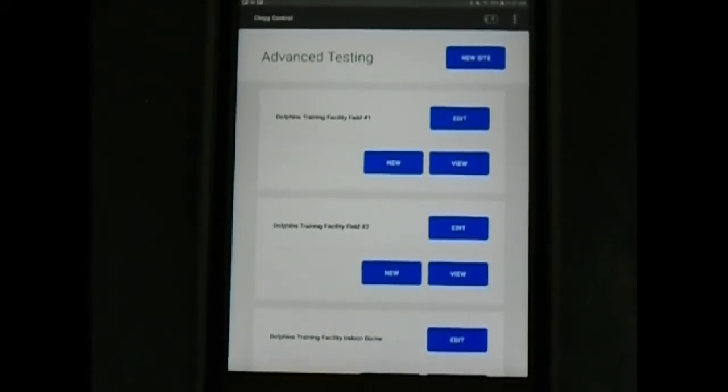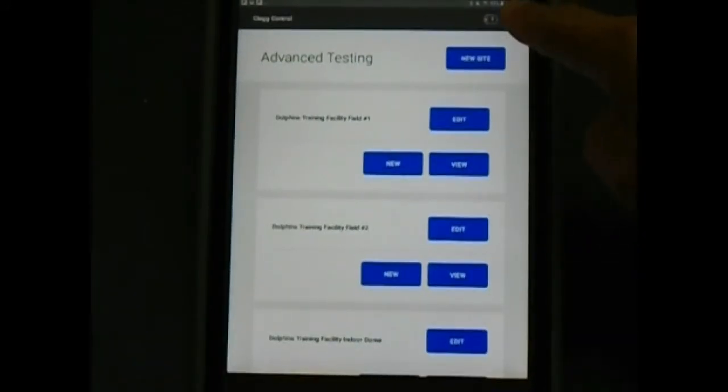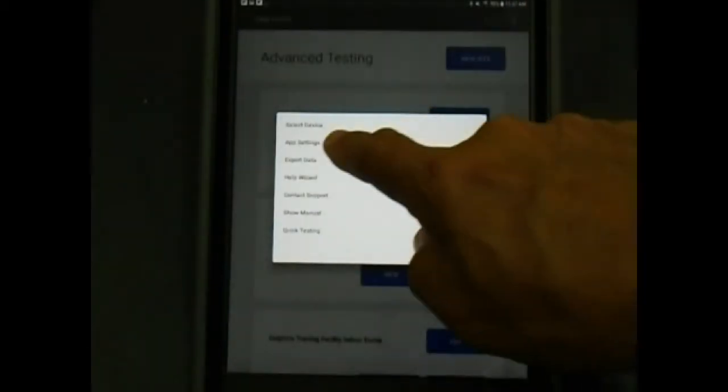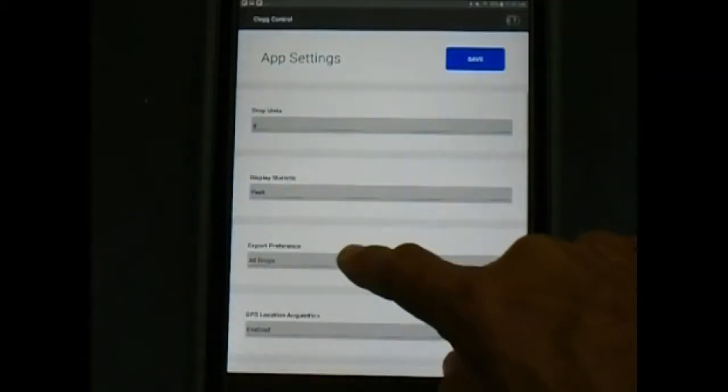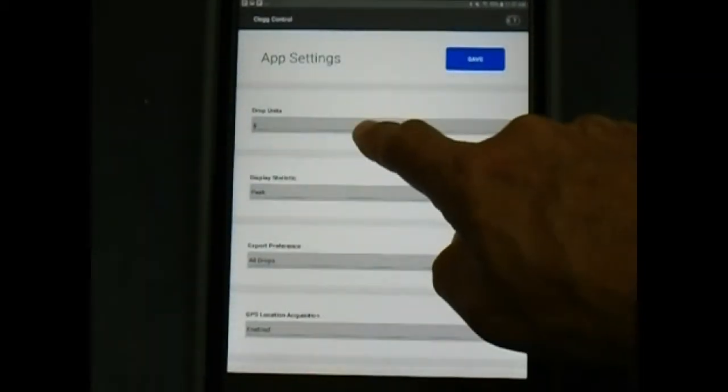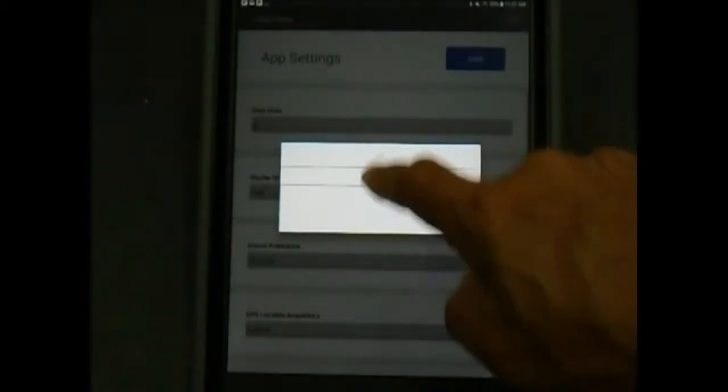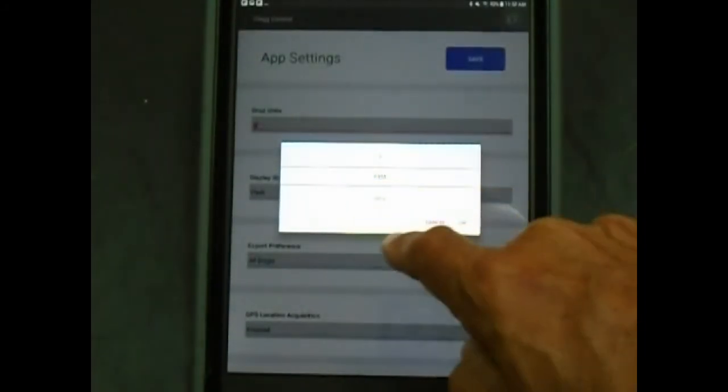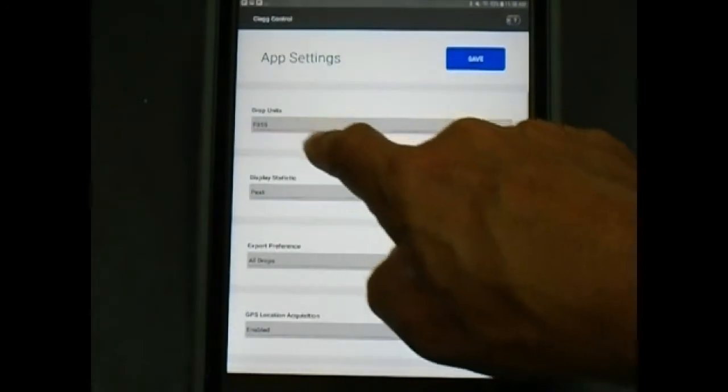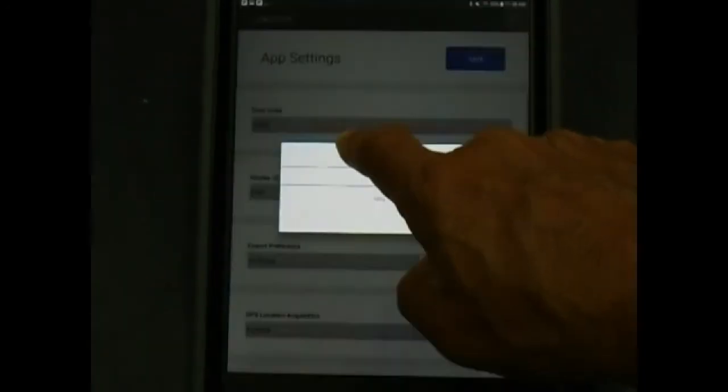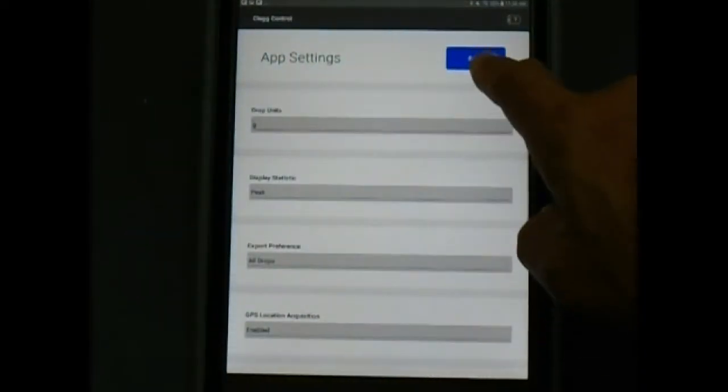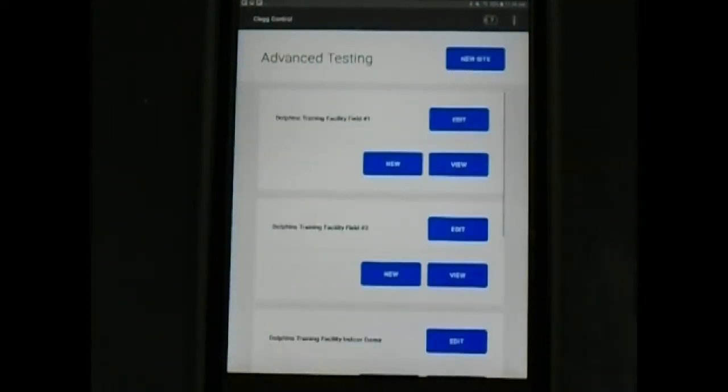Note, for Drop Units, you can also use F-355, which automatically converts your Gmax readings to F-355 equivalent readings by using the conversion formula included in the instruction manual. However, most testing with the Clegg is usually performed in G for gravities. The NFL reports their readings in gravities or Gs.